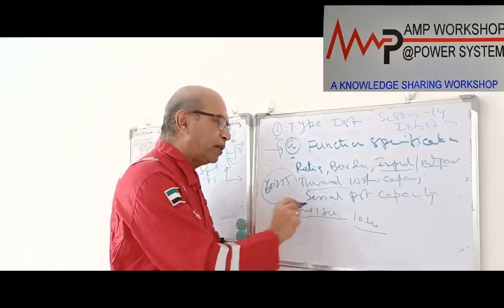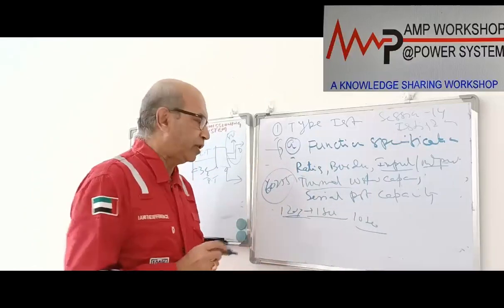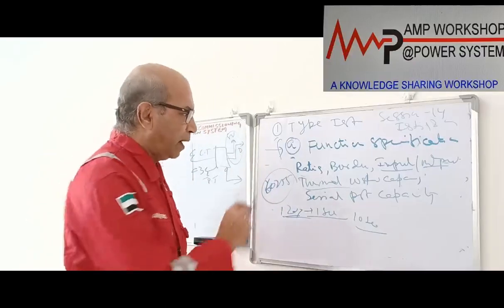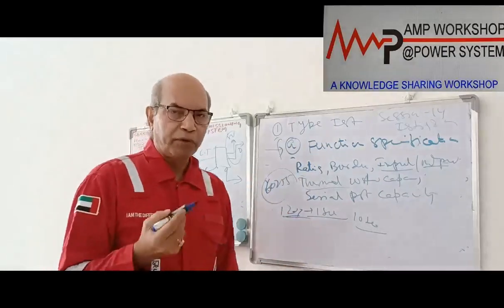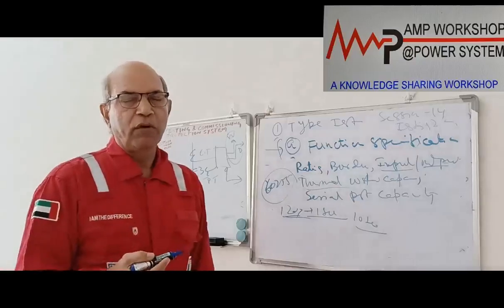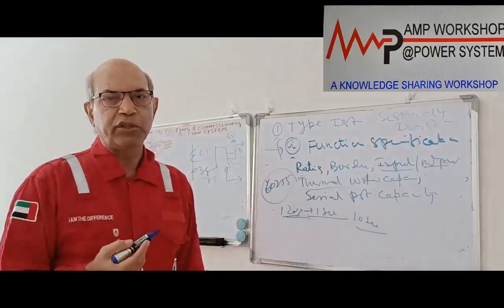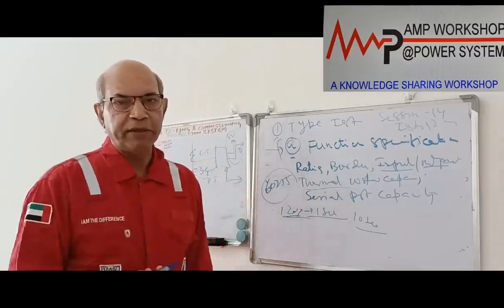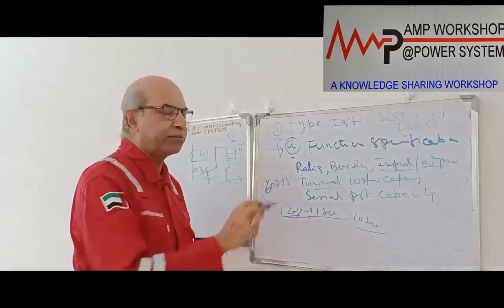And then the serial port capacity, we have a protocol mentioned for how to do this serial capacity measurement in the same standard. We follow that standard. After we carry out all the tests, we take out the relay or protection device. Then we see if there are any traces of overheating, overstress, any twisting or any other damage, or any carbon deposition on the PCB. In the case of numerical relay, a lot of cards are there. Whether there is any damage in the card pin or anything, we check all this. And if nothing is there, then it is absolutely fine.